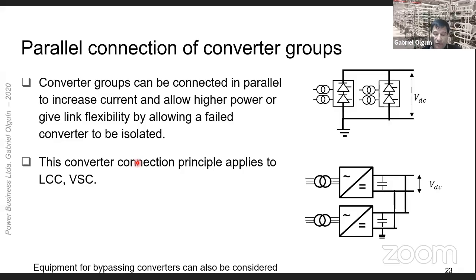A parallel connection of converters is also possible. Converter groups can be connected in parallel to increase current into the DC line for higher power, or for extra flexibility by allowing a failed converter to be isolated. Again, this converter connection principle also applies to LCC and VSC technology.